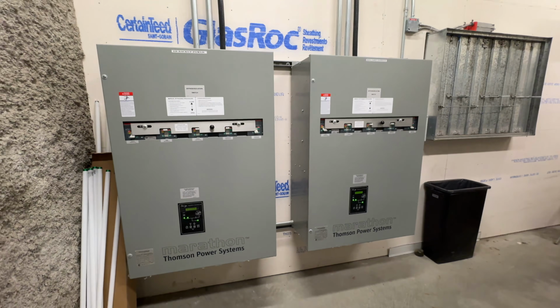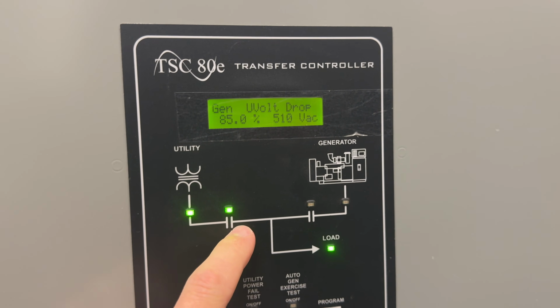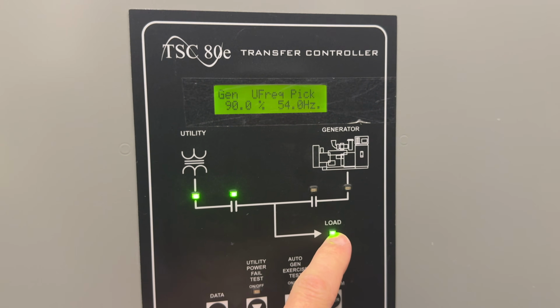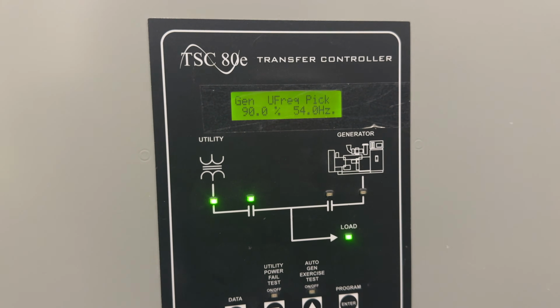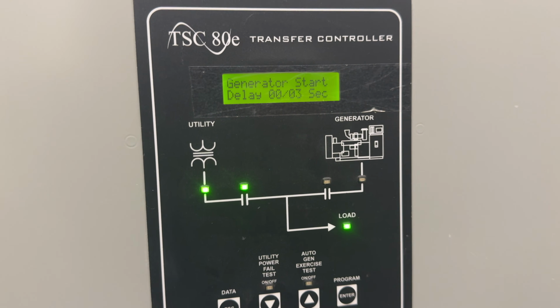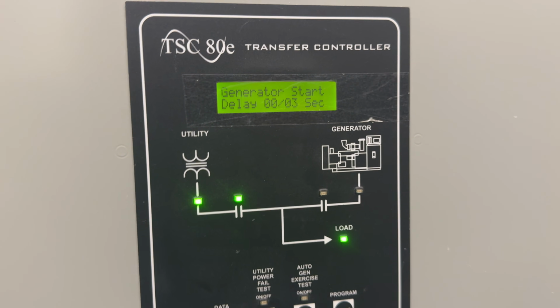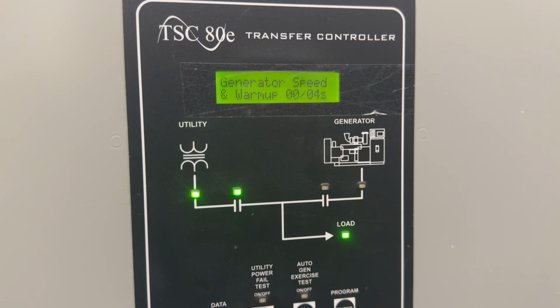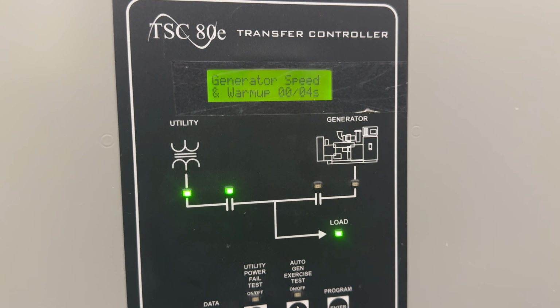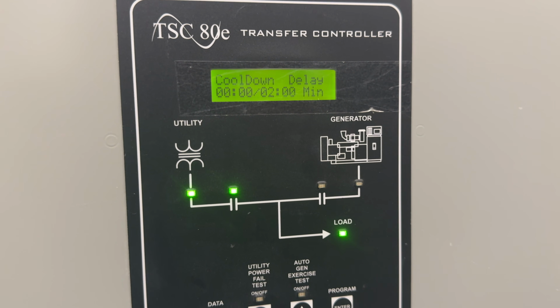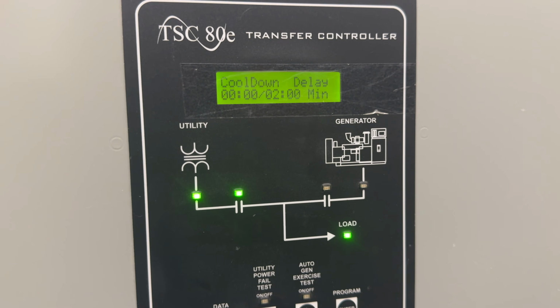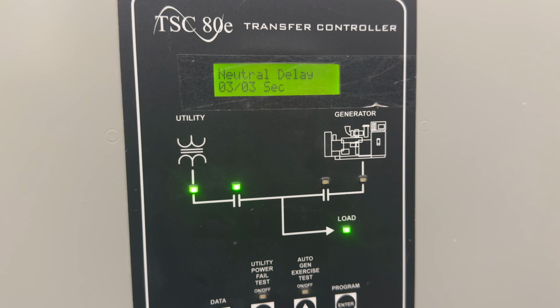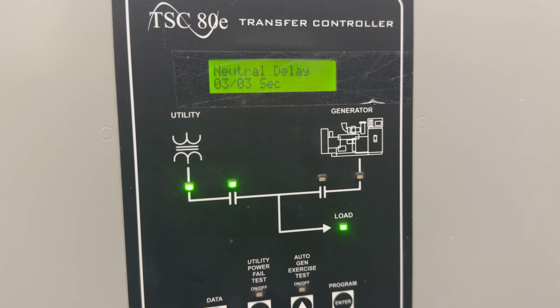Brief sequence of events here. We're powered off of utility, closed in on utility, going to the load. Our frequency pickup, 54 Hertz, 90%. We have a 3-second start delay, so power has to be out 3 seconds before we start. Our warm-up time is 4 seconds, so that's how much time the generator runs before transferring load. Cooldown time is 2 minutes. That means after power is restored, the generator won't go off for 2 minutes.